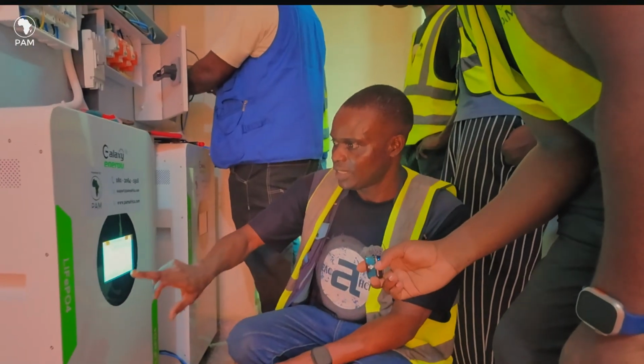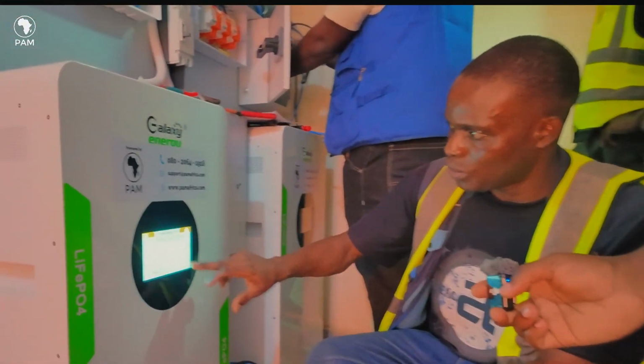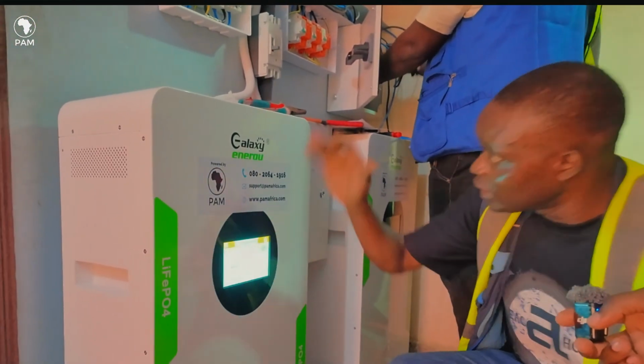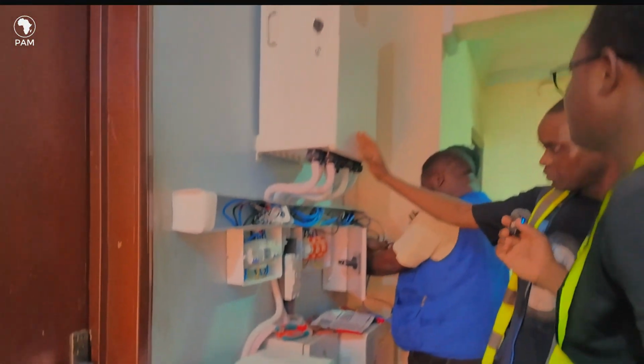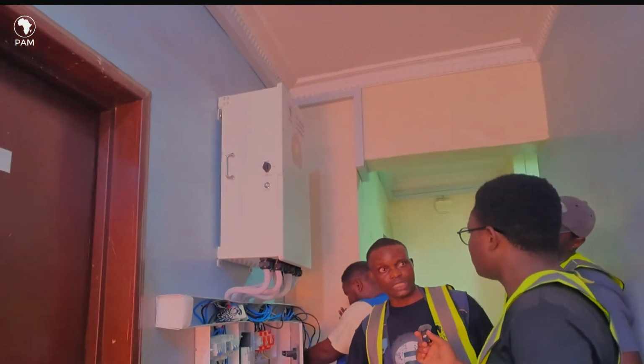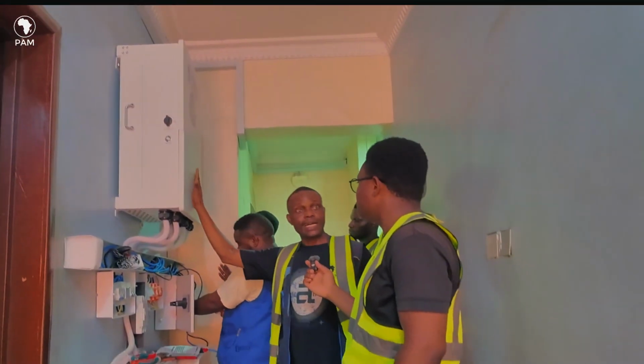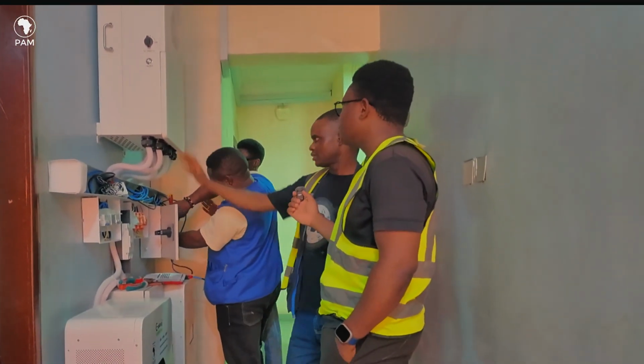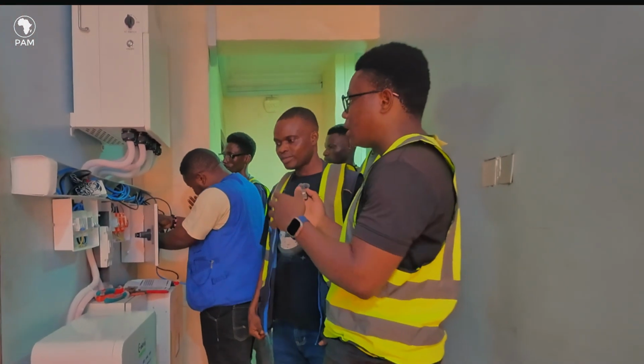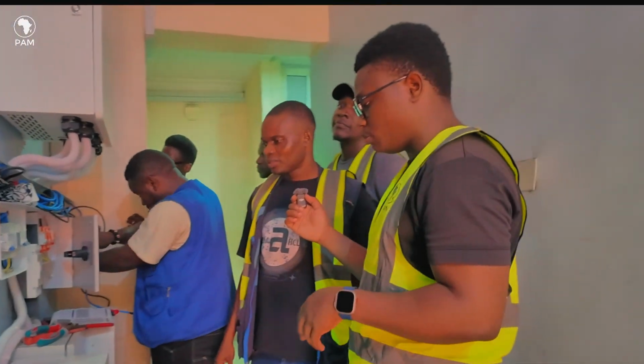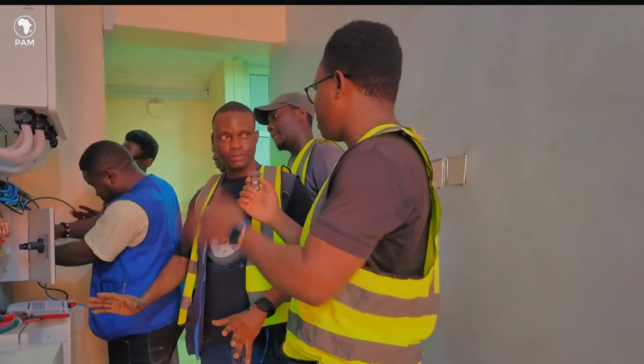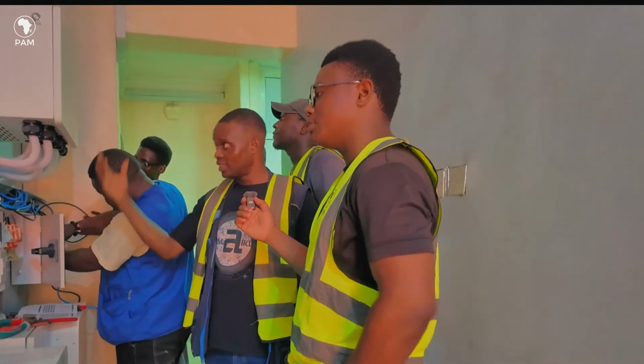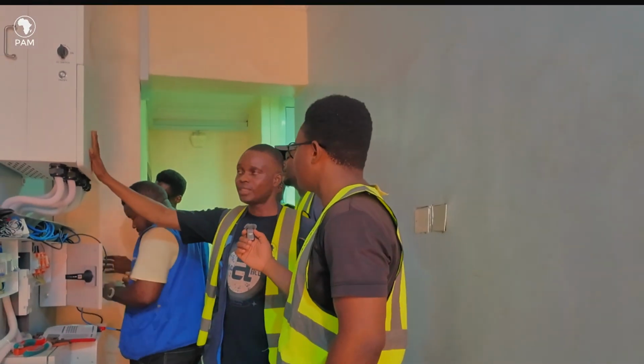That's just it, and it's actually touch screen. Aside from that, it also communicates with the battery using what we call the battery communication cable, embedded into the CAN port of the inverter. I always talk about battery communication and how the inverter needs to communicate with the battery - this one already has that communication running, based on the settings we've initiated in the inverter.